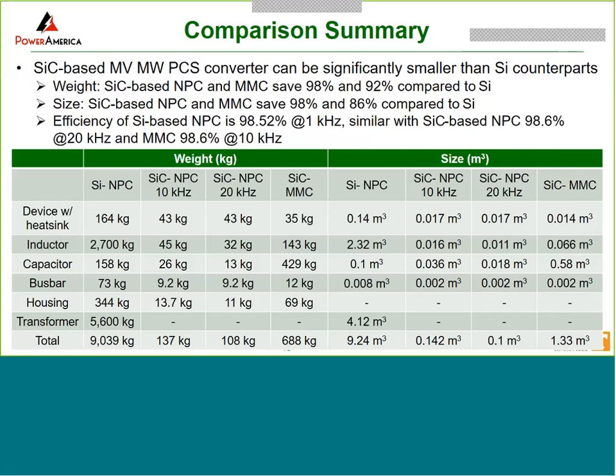Okay. The next question is, to achieve a 20 kV DC bus, is the speaker building a 5-level converter using 10 kV silicon carbide MOSFETs? Sorry, I didn't quite get that. Can you repeat? Okay. To achieve the 20 kV DC bus, are you building a 5-level converter using 10 kV silicon carbide MOSFETs? Right, it's not 20 kV, it's 25 kV. That's why we use 5-level. The reason is we cannot use third harmonic injection in this case, so we have to leave some margin for it.